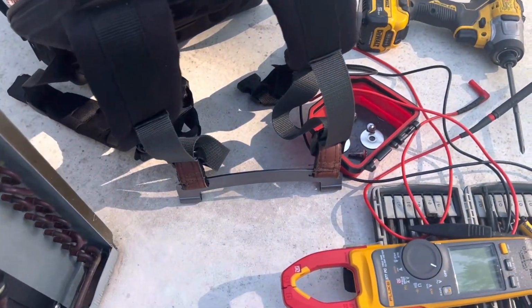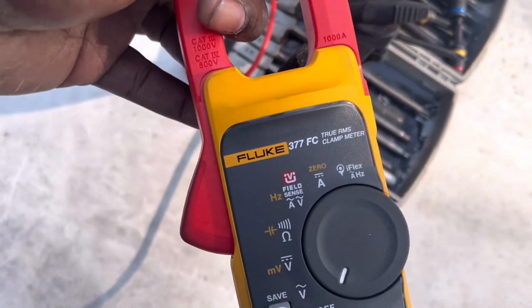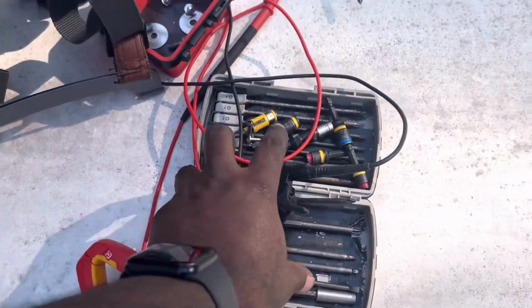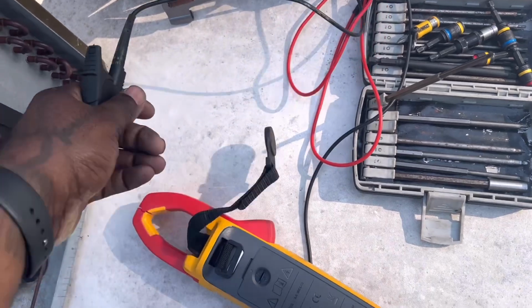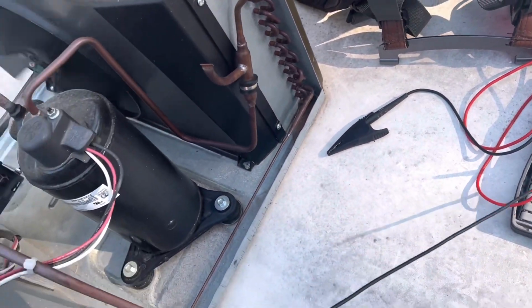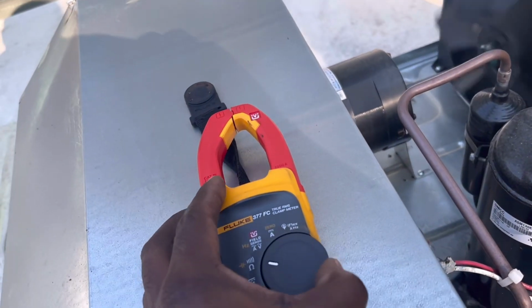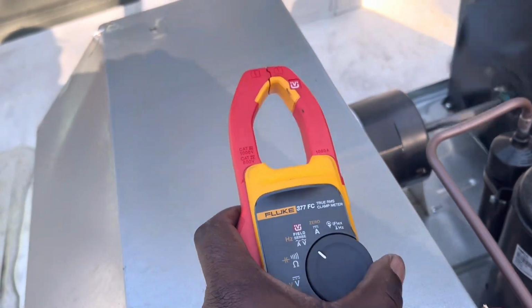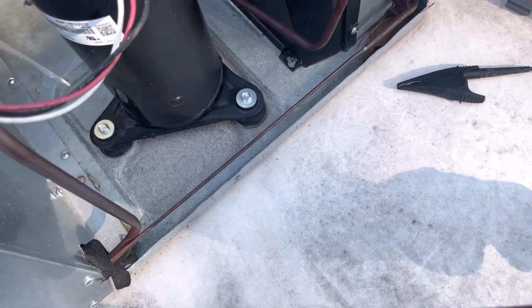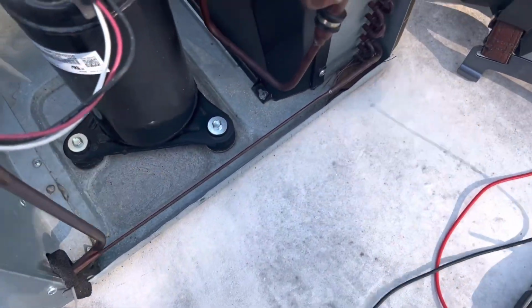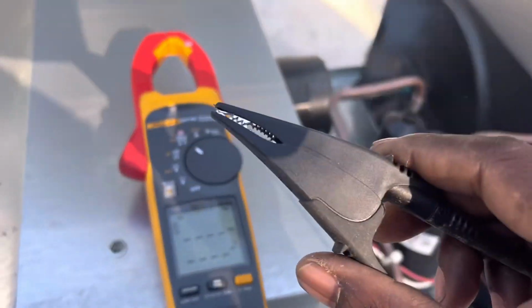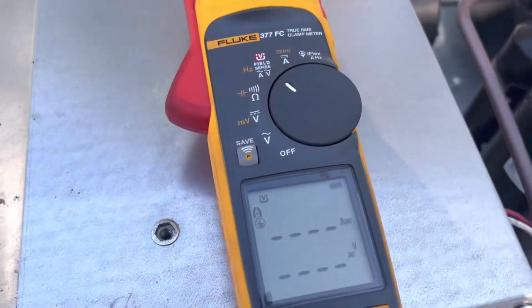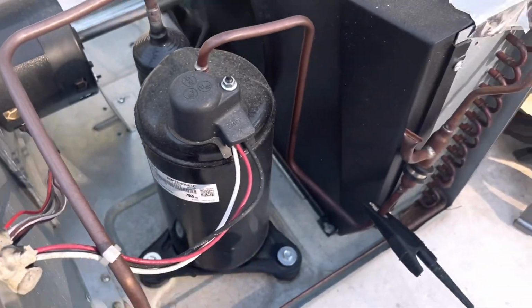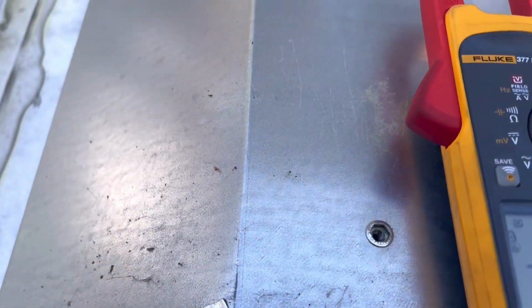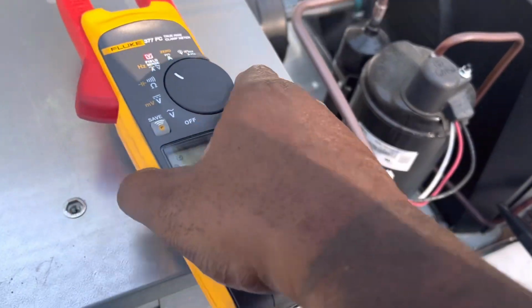Now, because I have a high-end clamp meter, this Fluke 377 FC, I don't have to pierce any wires or make any crazy connections. I can simply set up my meter, and I'm going to use the field sense working with AC. This does require you to have the ground hooked up so you can get your hertz. So I have the ground lead here, and I'm going to connect that just to any of the copper, because that's going to be a good ground. And then I'm going to test my wires on this compressor.